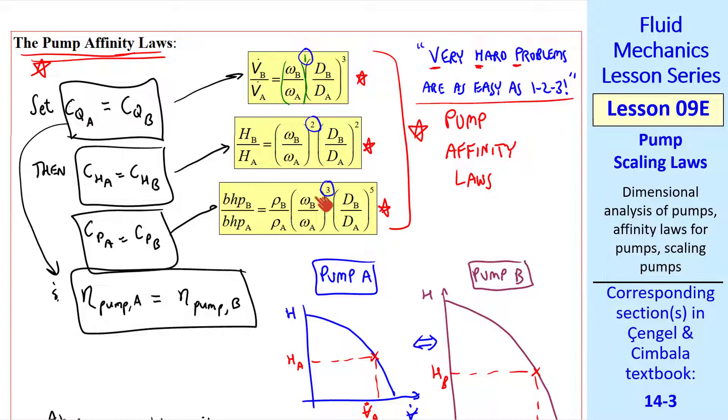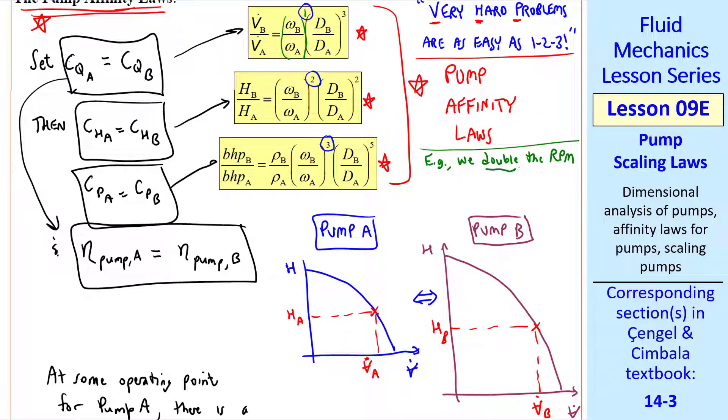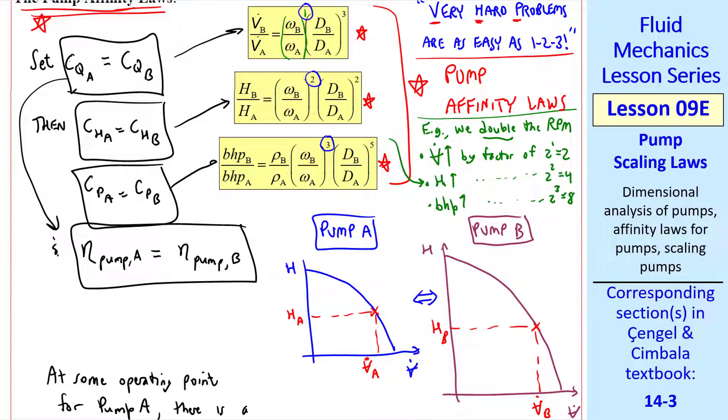For example, if we double the RPM, just increase the RPM by a factor of two, we see from these equations that V dot goes up by a factor of two to the one or two, net head goes up by a factor of two to the two equal four, and BHP goes up by a factor of two to the three or eight. So if you have the same pump and all you do is double the rotation speed of the impeller, you get twice as much volume flow rate and you produce four times as much head, but it's going to cost you eight times as much power.